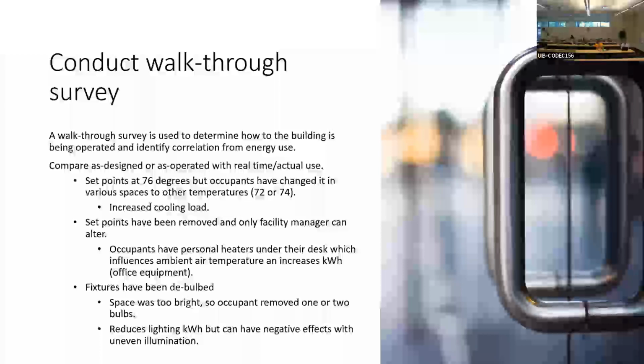Another thing facility managers have tried is removing the thermostats, or at least disabling their operation, so people think they're changing the temperature but it actually has no effect. People will generally notice it's not getting colder or warmer, so one workaround is personal heaters under their desks. That influences the ambient air temperature, which throws off the HVAC scheduling, and increases kilowatt hours because it's additional office equipment that wasn't accounted for.